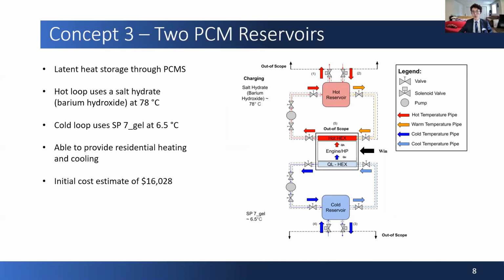Concept 3, two phase change material reservoirs, uses latent heat storage for both loops, with approximate dimensions being 3.5 meters by 3 meters by 1.1 meters. For the hot loop, a barium hydroxide salt hydrate is used at its melting point of 78 degrees. For the cold loop, a phase change material called SP7 gel by the company Rubitherm is used at its melting point of 6.5 degrees Celsius.